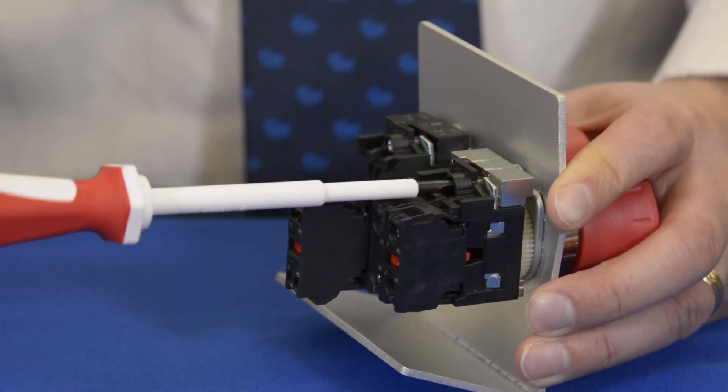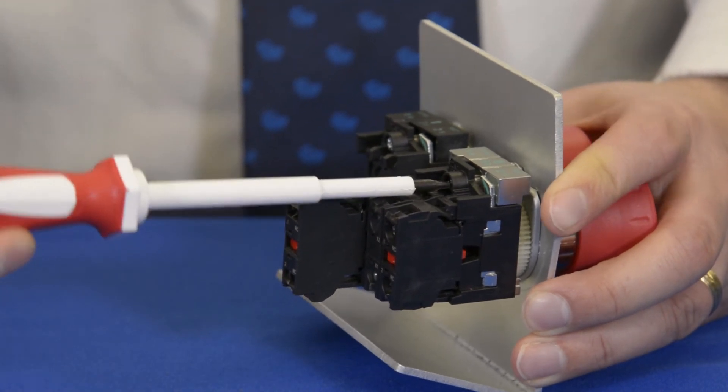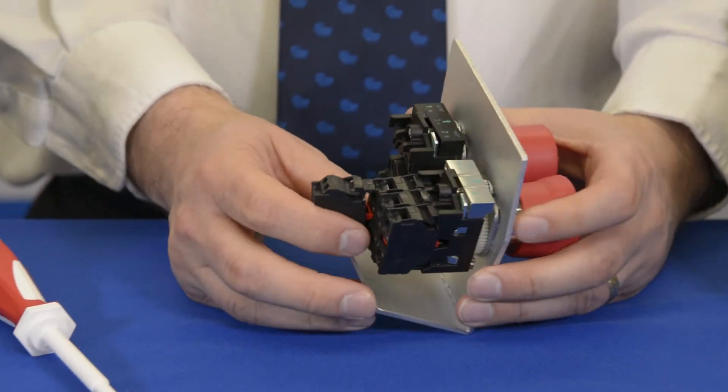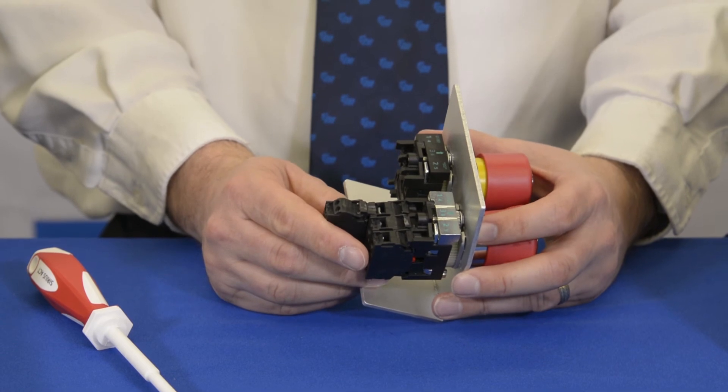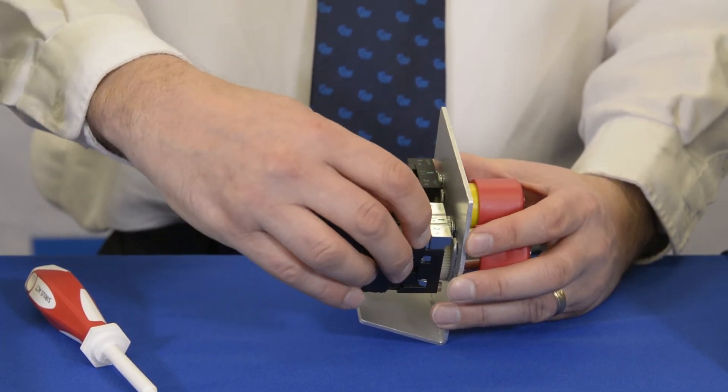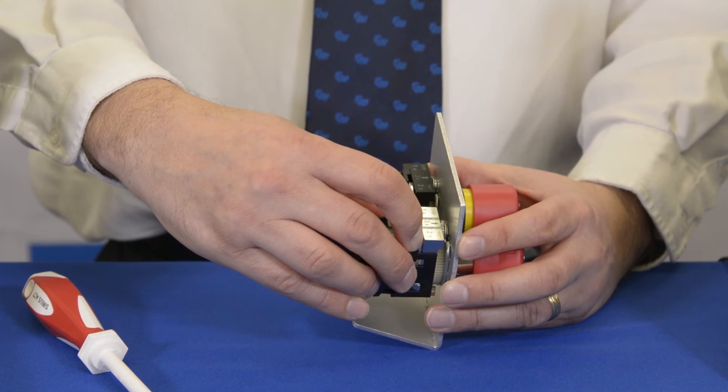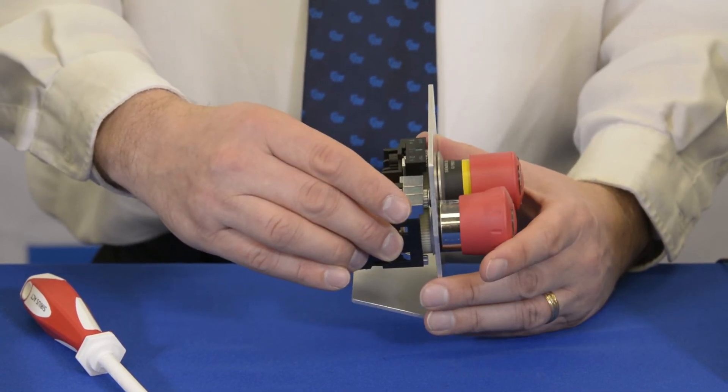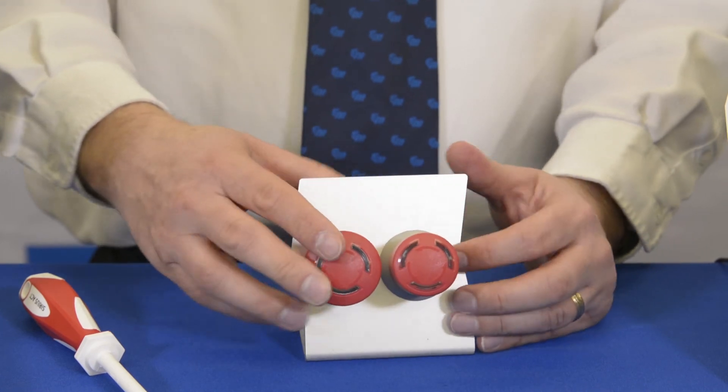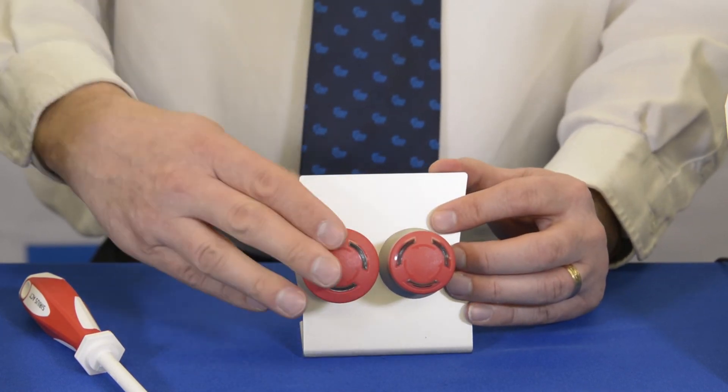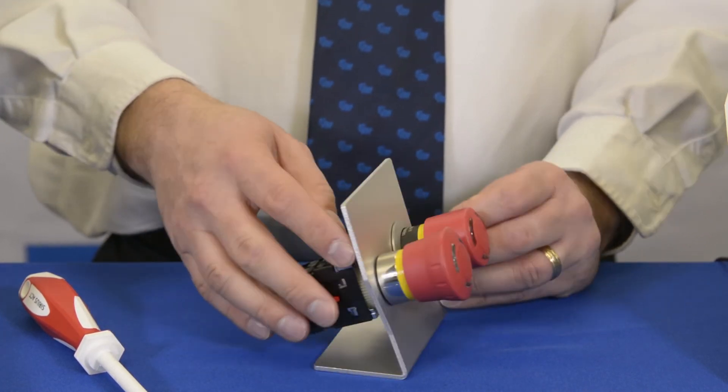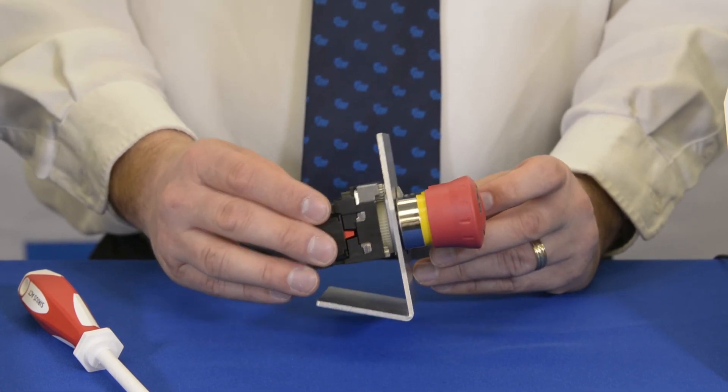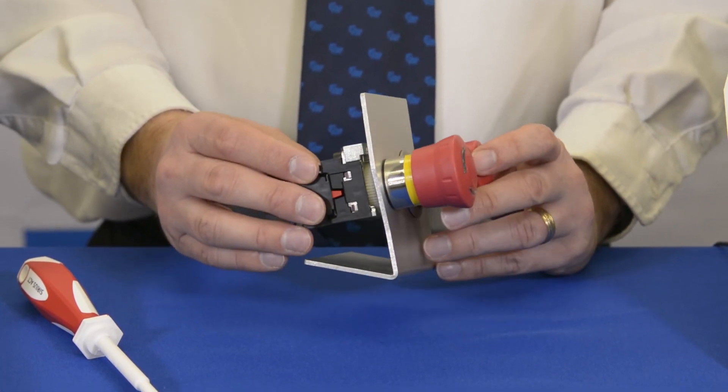When this screw is tight, a couple things happen. Number one, I've just grounded that assembly together. I've also made it so that that latch mechanism will no longer allow me to release the contact blocks from the back of the operator. And furthermore, this happens to be a twist-to-release device. Over time, this is not going to come loose. So you won't have to worry about those wires getting tangled up like our competitors.